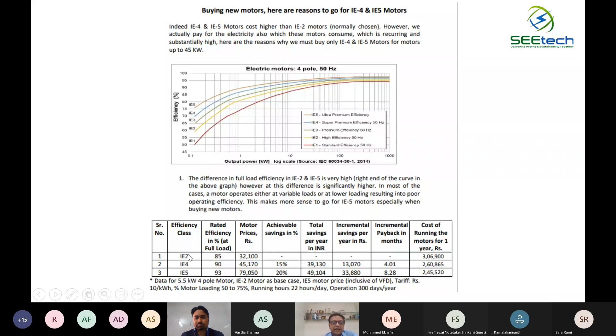Let me explain this example. There is an application wherein we are trying to compare the base case, and then we are trying to change it by, instead of buying an IE2 motor, thinking of IE4 and IE5 motors. These are the rated efficiencies: 85%, 90%, and 93%. Now look at the cost of the motors: this is around 32,000, this is 45,000, and this is around 79,000. You'll obviously feel that when I can do my job with 32,000 rupees, why should I put 79,000?